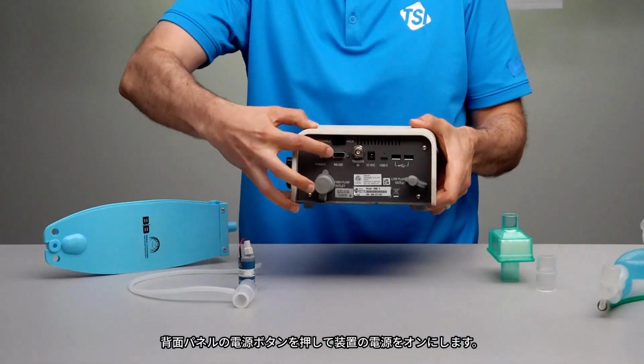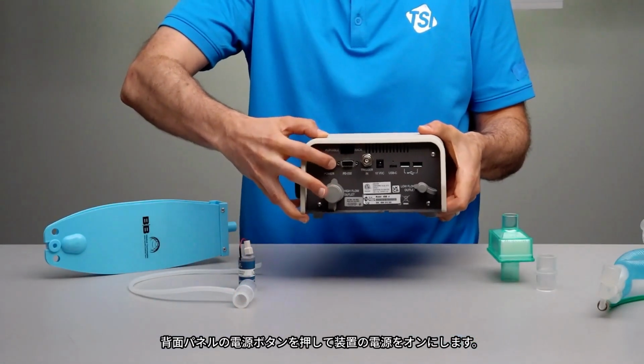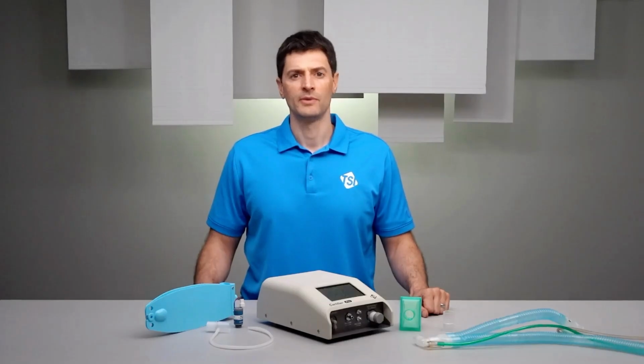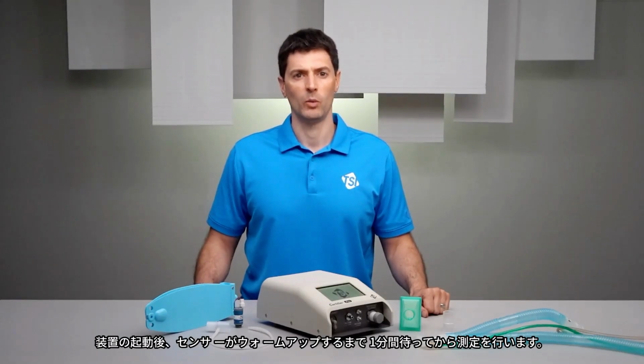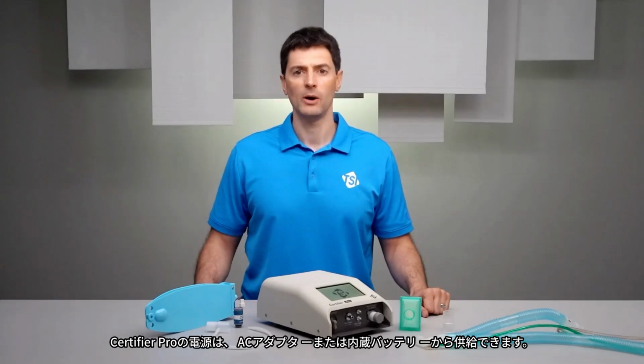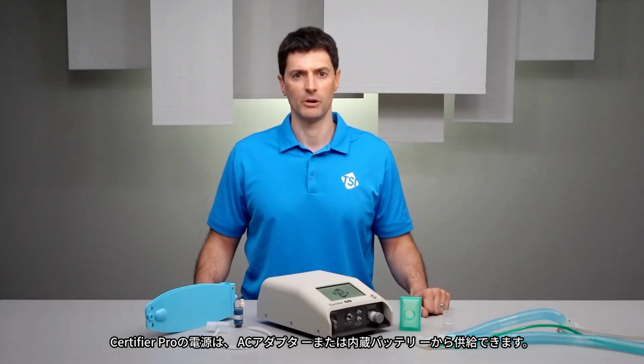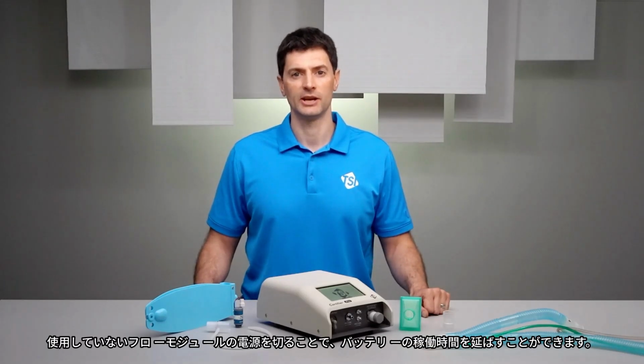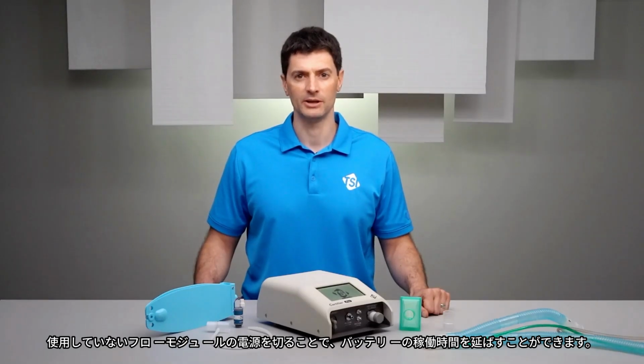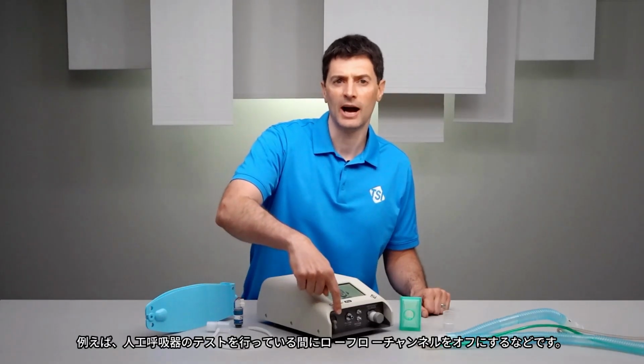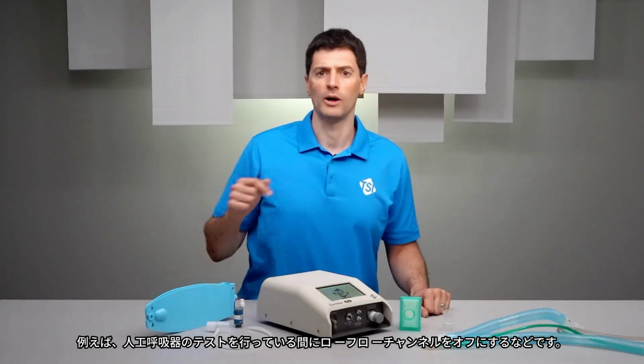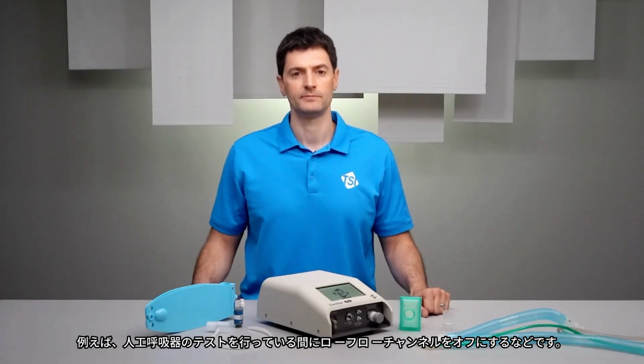Press the power button on the back panel to turn the instrument on. After the instrument boots, wait 1 minute for the sensors to warm up before taking measurements. Power can be supplied to the Certifier Pro using the AC power adapter or from its internal battery. Battery operation can be extended by powering off a flow module if it's not being used, such as toggling off the low flow channel while you're performing ventilator testing.